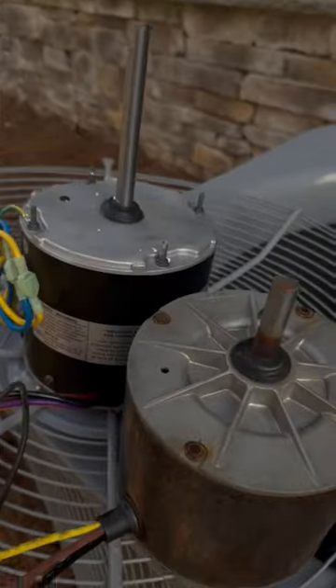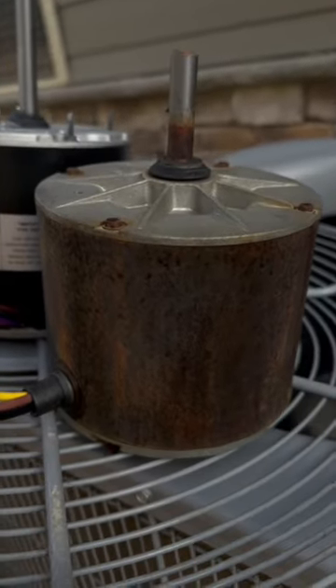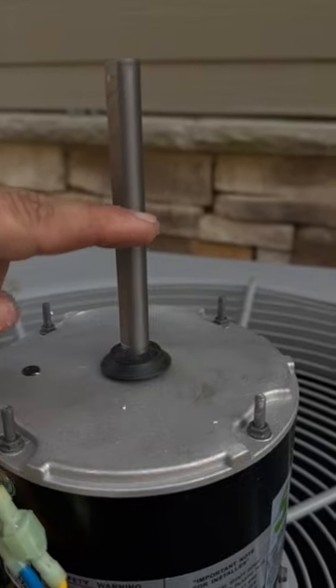What's up guys, got a quick solution to show you. If you're changing a condenser fan motor and the shaft seems to be too long and it hits the compressor before it actually sits down on the unit, you can see the difference in the universal and the original motor. Find the length that your shaft needs to be at.